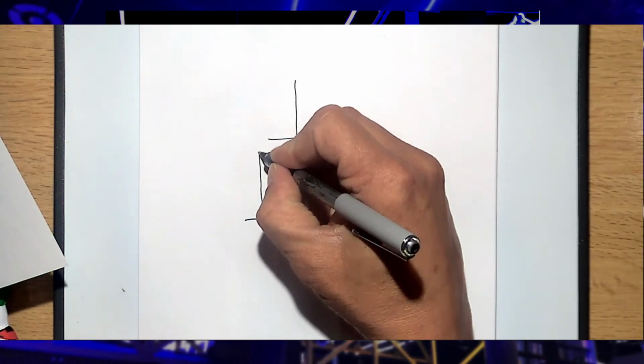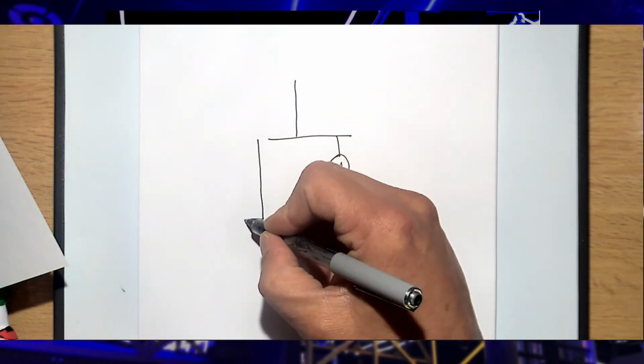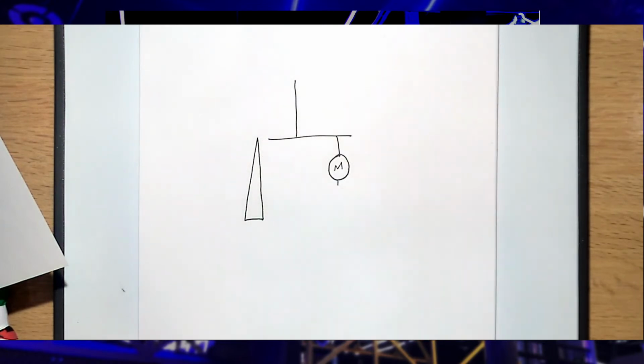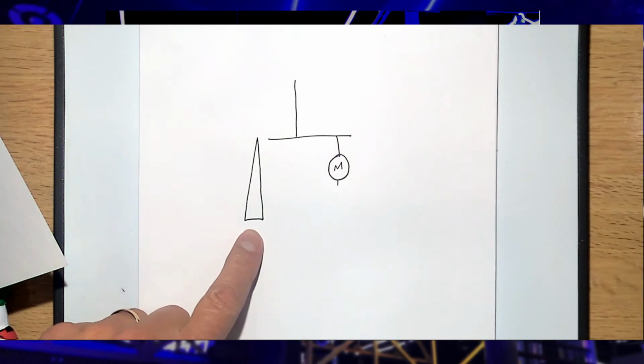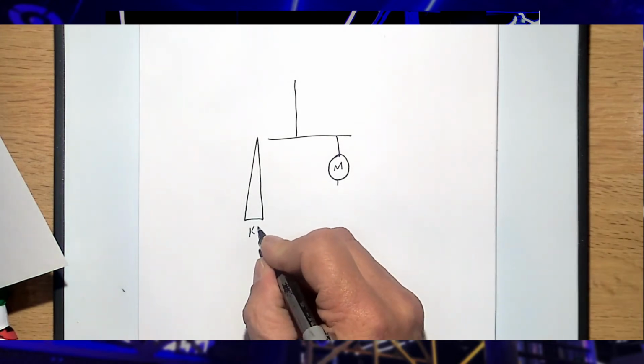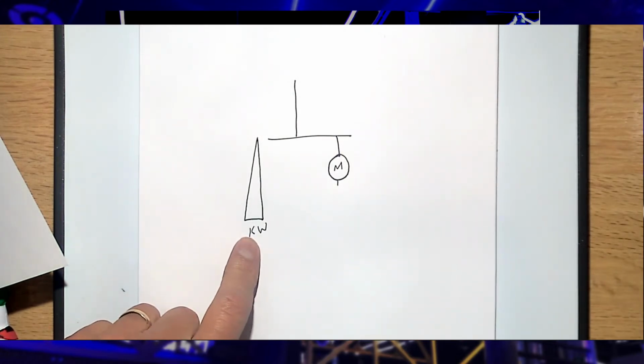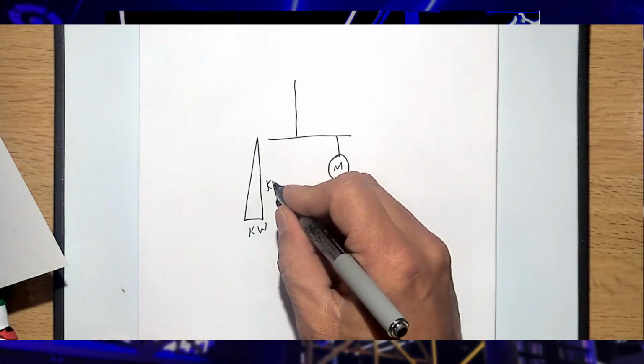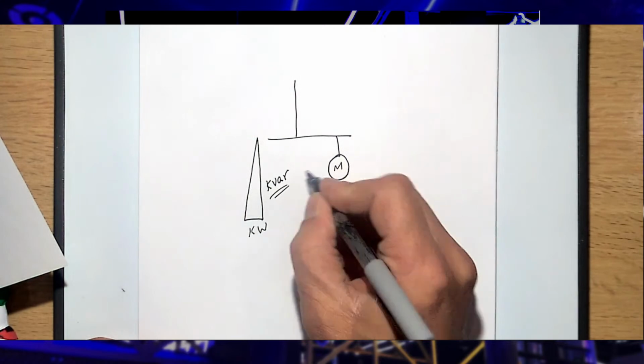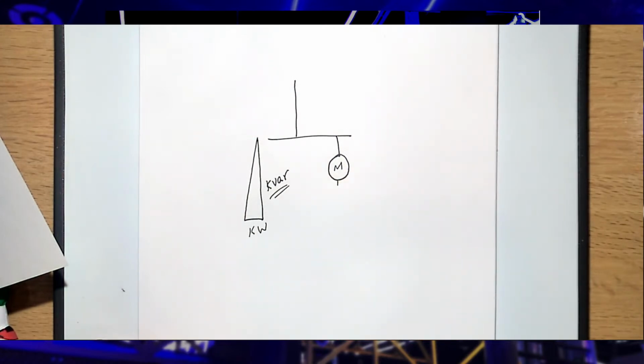For an unloaded motor, it's probably heavily reactive, right? Yeah, mostly reactive. So that motor only has a little bit of kilowatts, I'm even exaggerating a little here. The only reason it has kilowatts at all on an unloaded motor is it has to spin the shaft, overcoming friction, which is very, very little. But it needs reactive power to run the motor, because it has to magnetize the motor.